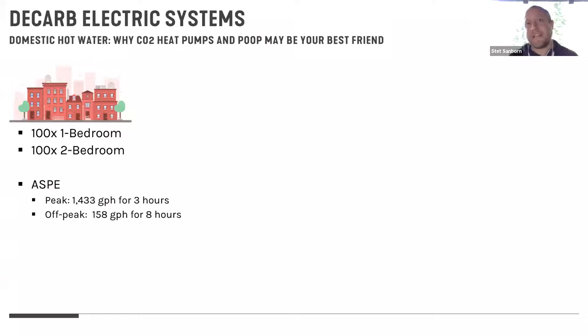And so we're sizing air source heat pumps. You will never ever see a cost-effective solution that does not involve storage. We have projects with gas-fired appliances, gas-fired condensing boilers. I have even seen a project that did point of use instantaneous water heaters, no storage, but the gas line going to that building, I could have crawled through. It was amazing. But for every heat pump project, you are going to match it with storage.